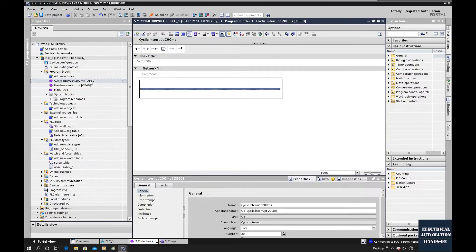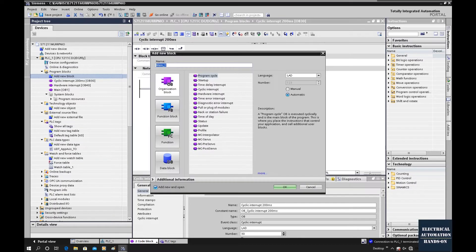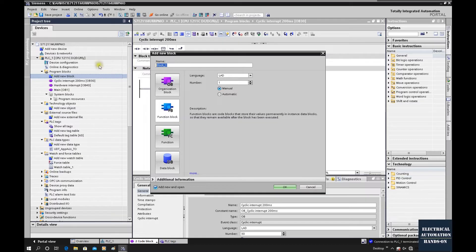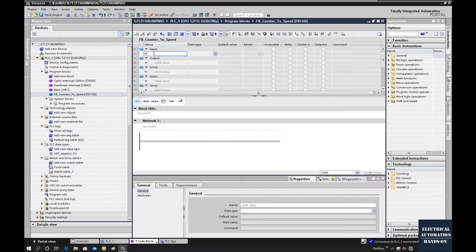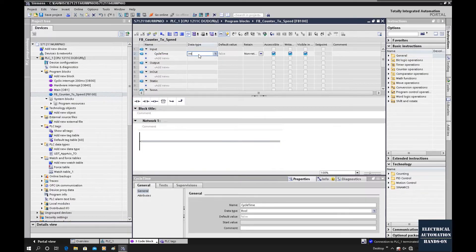Then we create a function block for future project reuse. Add a new block and name it 'FB_Counter_to_Speed', FB100. Since FB100 will be called by OB30 every 200 milliseconds, to allow flexible code I will add an input channel. This 200ms value could be a parameter — if in the future you use another cyclic interrupt, for example 100ms, this function block can still work. I will name this input 'Cyclic_Time', data type integer.